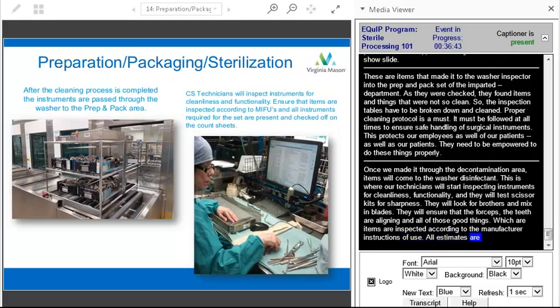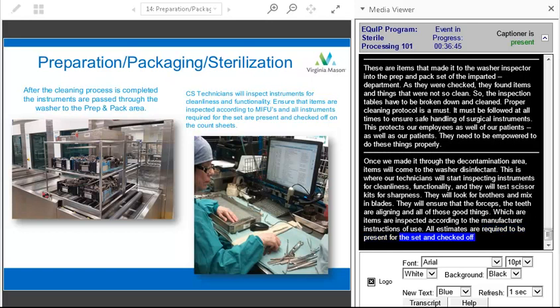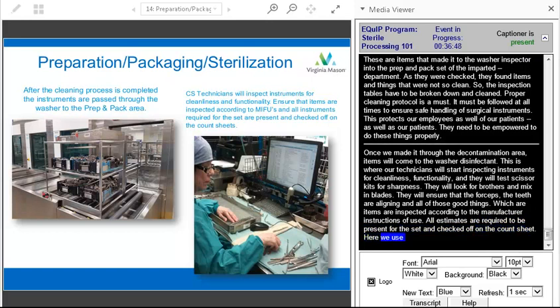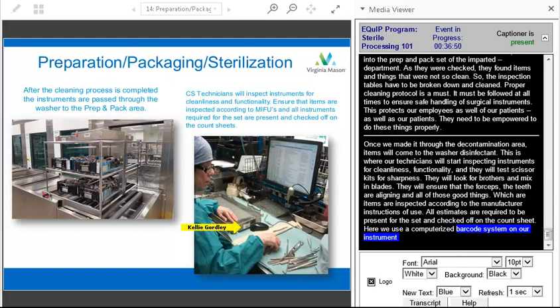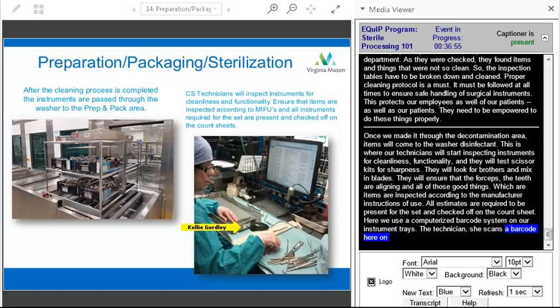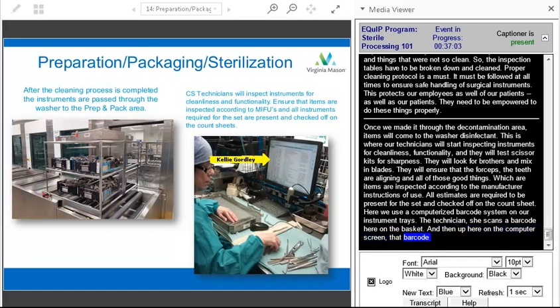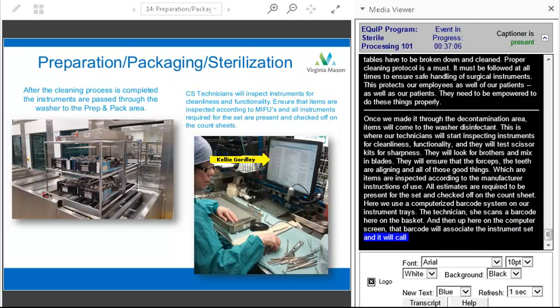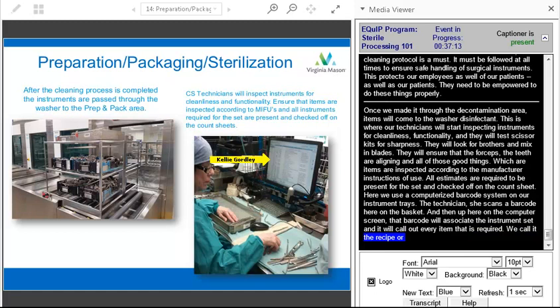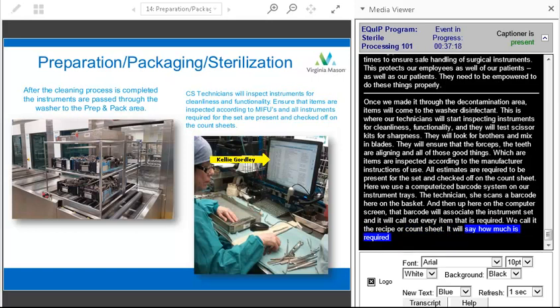Here we use a computerized barcode scanning system on our instrument trays. And so the technician here, she scanned the little barcode that's here on the basket, kind of like they do at the grocery store. And then up here on the computer screen, that barcode will associate that instrument set, and it calls out every item that's required, what we call the recipe or the count sheet. So it'll tell you how many clamps, scissors, forceps, and whatnot are required for that tray. And so as they go through, they will click off everything that they've counted and inspected.